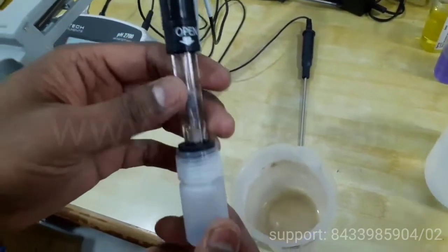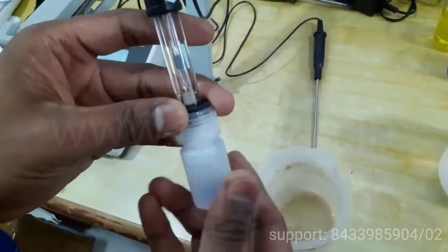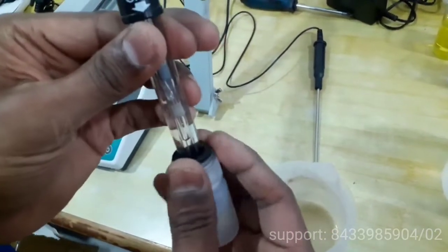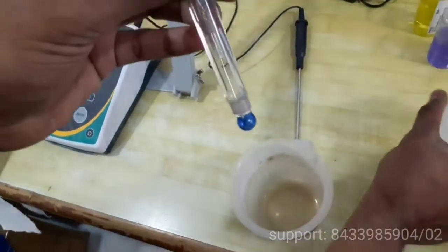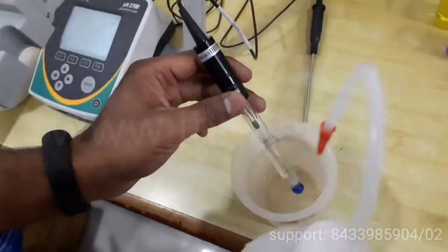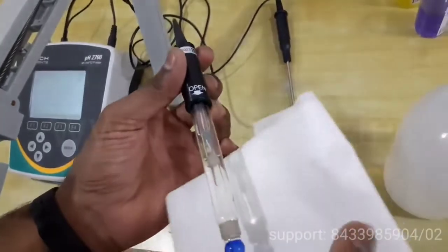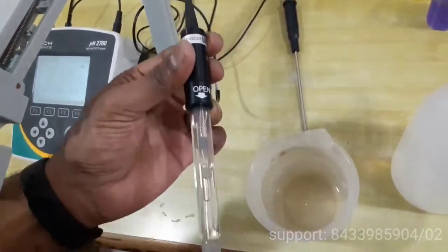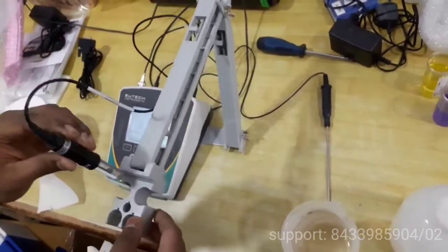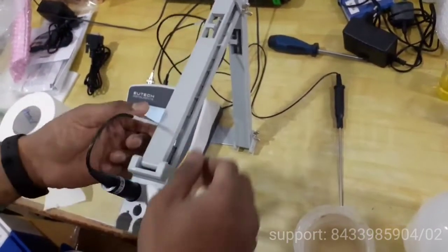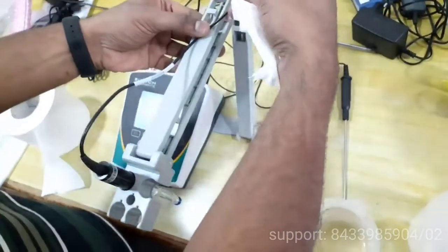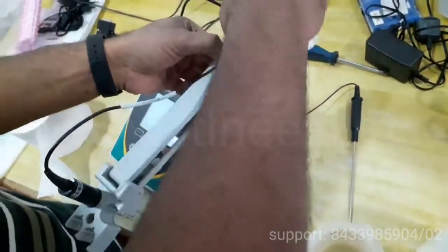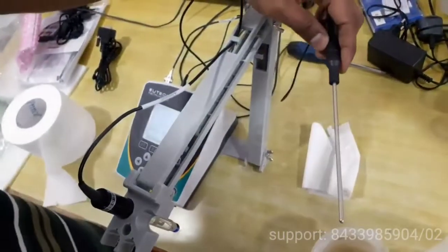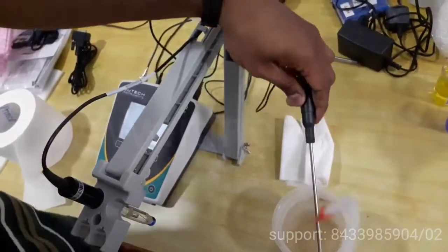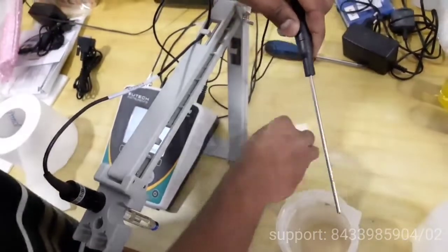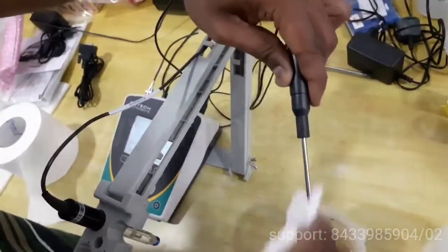Before taking a reading, first you have to clean the electrode. For that, you have to unscrew this storage bottle and pull it down. Then clean it with distilled water and dry it with tissue paper. Then you can attach it to the electrode holder by placing it over here and putting the excess wire over here in this notch. Then you have to clean this ATC probe also, before and after taking readings, with distilled water and tissue paper.